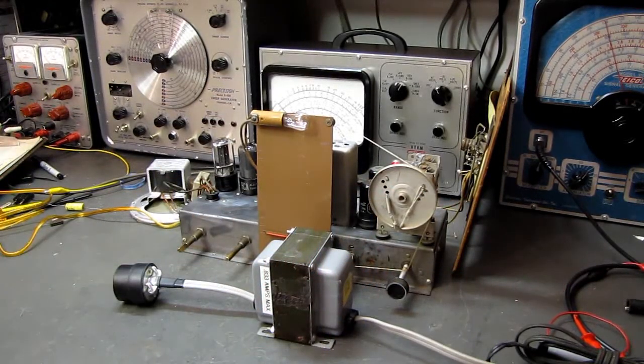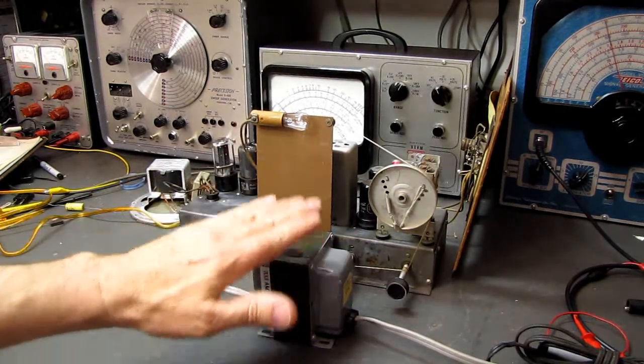A Variac is not an isolation transformer. I've had this argument with so many people, and they insist a Variac's an isolation transformer. It is not. A Variac is an auto transformer, which is referenced to the line. They do not isolate unless used in conjunction with an isolation transformer.